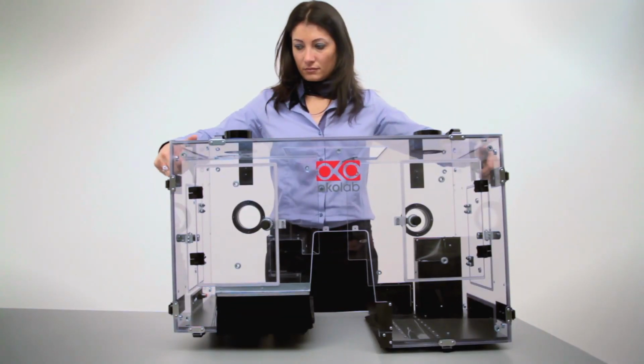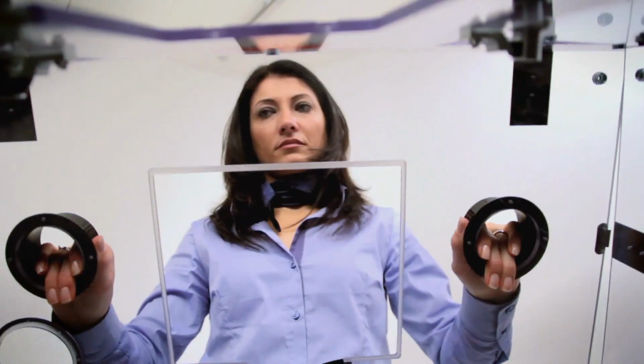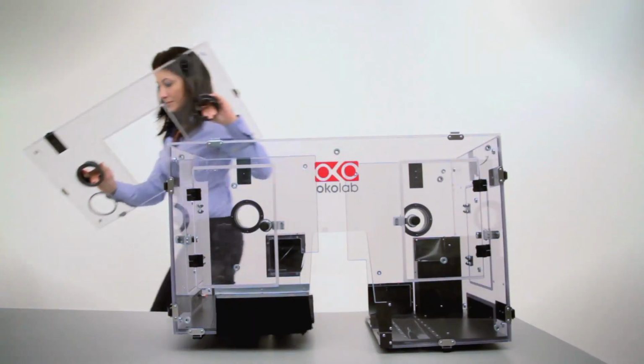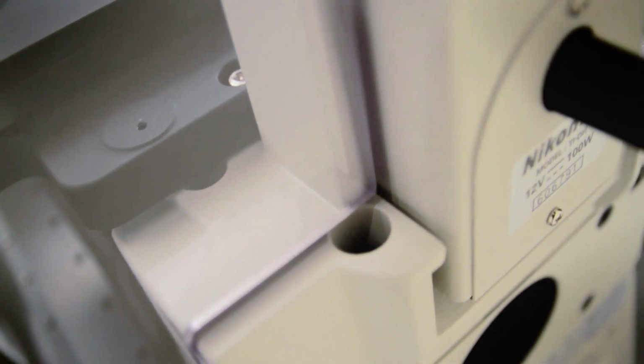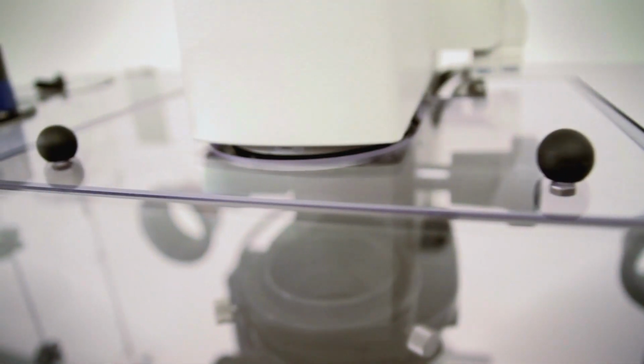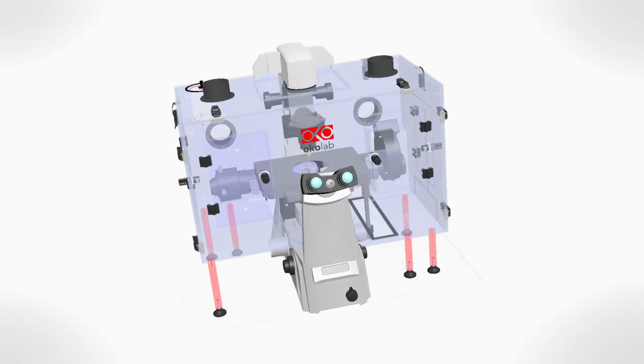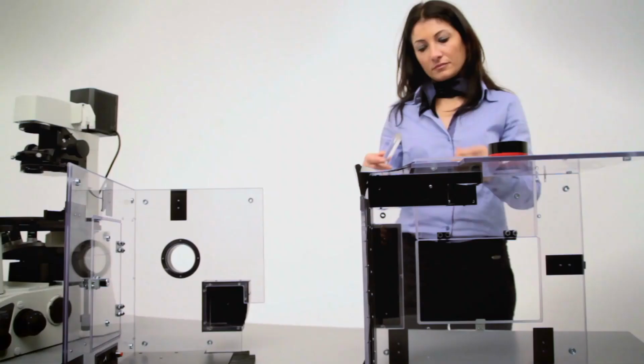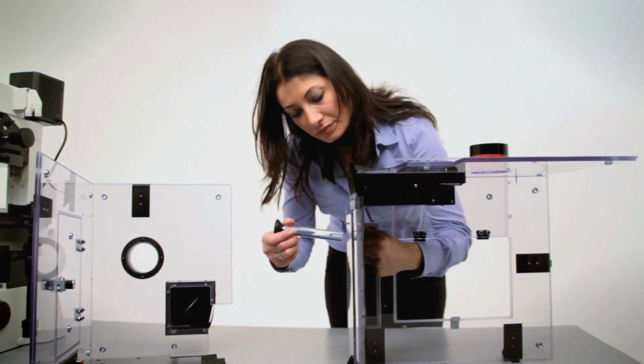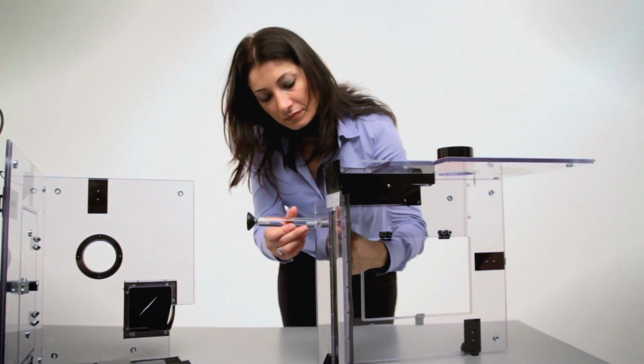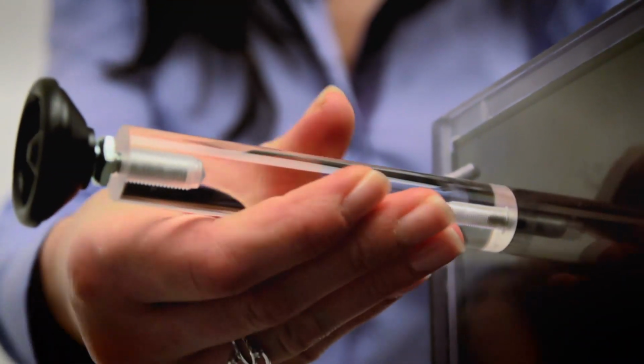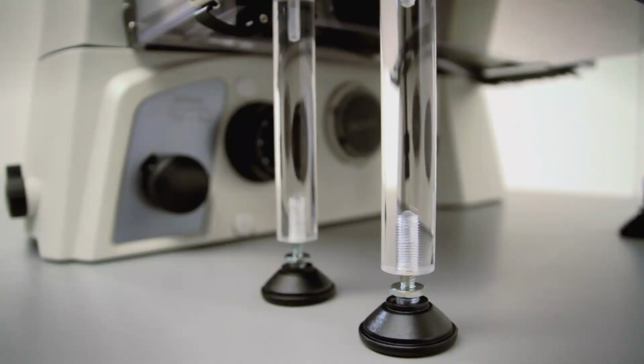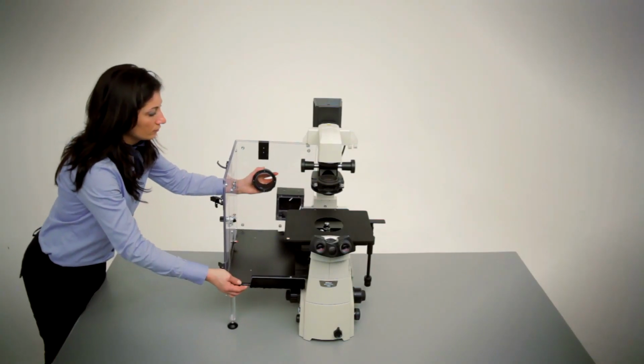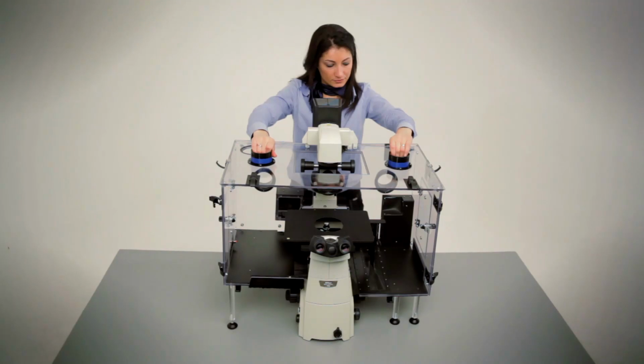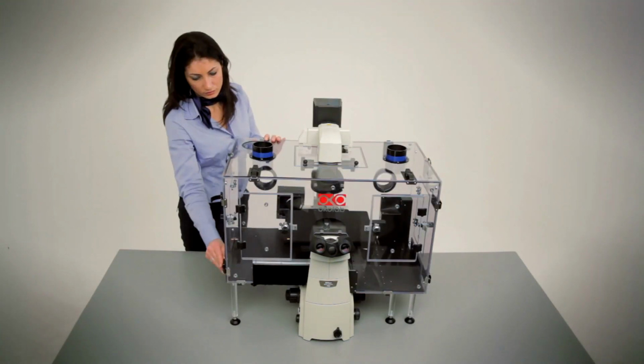Position the enclosure on a clear table and disassemble the top and front panel. The shape of the enclosure depends on microscope configuration and on the attached equipment. The enclosure is generally supported by 6 posts. Left and right posts may have different lengths. Attached to the posts, you will find the screws needed to fasten the supporting posts to the bottom panel of the enclosure. Position the left and the right block around the microscope, then position the top and front panel.